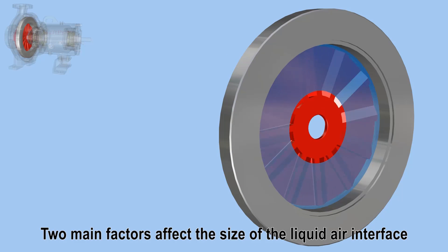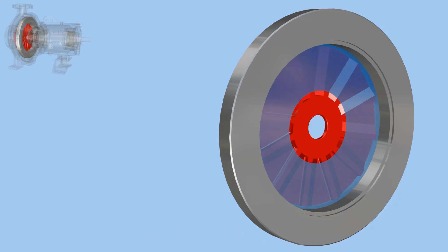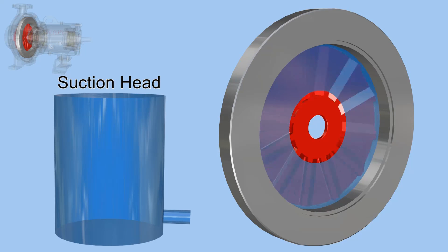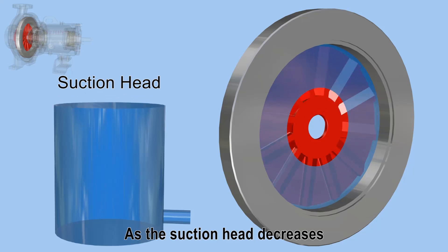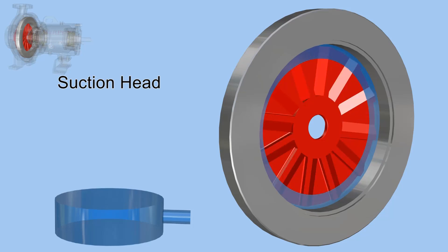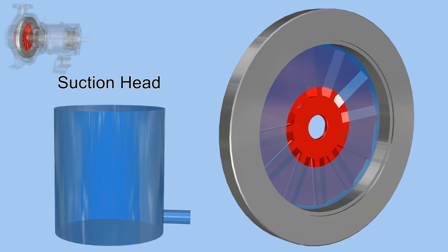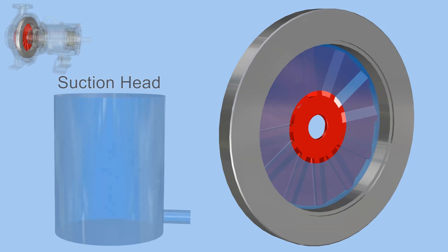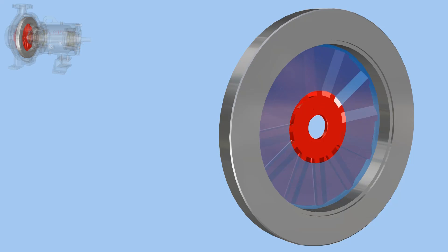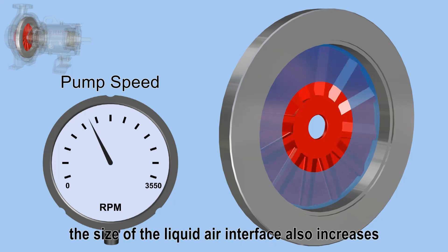Two main factors affect the size of the liquid air interface: suction head and pump speed. As the suction head decreases, the size of the liquid air interface increases. As the speed of the pump increases, the size of the liquid air interface also increases.